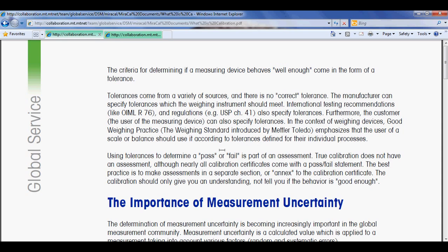So using tolerances to determine a pass or fail is part of an assessment. So true calibration does not have an assessment, although nearly all calibration certificates come with a pass or fail statement. It is important to understand that the ACC certificate will separate calibration and assessment. So it says here, the best practice is to make assessments in a separate section or annex to the calibration certificate. So the calibration should only give you an understanding, and it should not tell you if the behavior is good enough. That good enough or pass or fail can come in the form of an assessment in an annex to the calibration certificate. Okay?